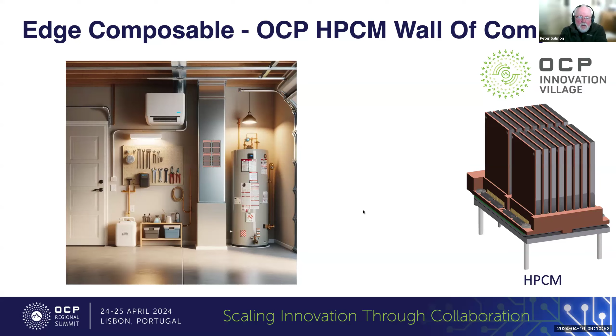Okay, so now I talk about the power delivery. I reference the Blackwell 2.5 meters, whereas we're 0.2 of a meter. So I just show in this diagram, the facility power is literally a couple of inches away from the chip power, and then we've got some routing, so we're less than 10% of the routing of the power, so the copper losses are a lot less, and it's lower cost because you use less copper, right?